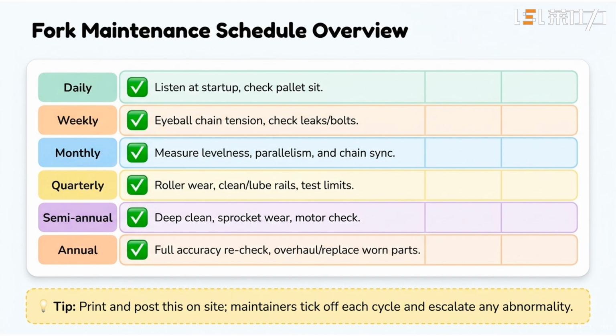This page is the complete maintenance schedule for the fork, from daily to annual. What each cycle needs is at a glance. Daily, listen to it run. Weekly, eyeball the chain. Monthly, measure levelness, parallelism and chain sync. Quarterly, check rollers and limit sensors. Semi-annually, deep clean. Annually, a full overhaul. The mark shows the cycles where accuracy rechecks are the focus. Print this table and post it by the panel, ticking off each task so nothing is missed.